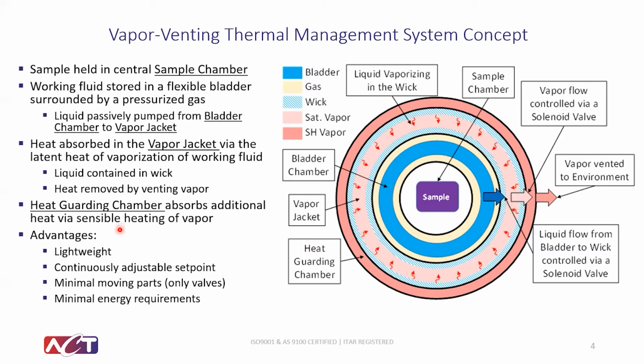There are several advantages of this concept. It is lightweight. It has a continuously adjustable set point. The temperature control point can be any value by selecting the correct working fluid and the temperature or pressure at which you vent vapor. There are minimal moving parts and minimal energy requirements for the system to operate.